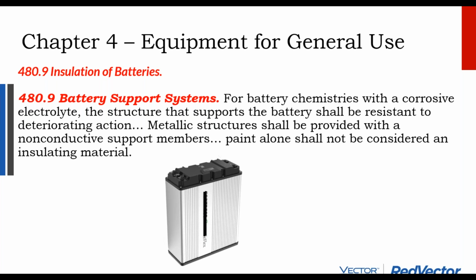So what do we do in that case? Well, we have to use rubber mats. If you're putting the batteries directly onto a concrete slab, that support structure has to be non-conductive, so you have to put a rubber mat between your battery and the concrete slab. You don't want to forget that step, because these batteries are very heavy and picking them up is not something that is particularly easy to do.